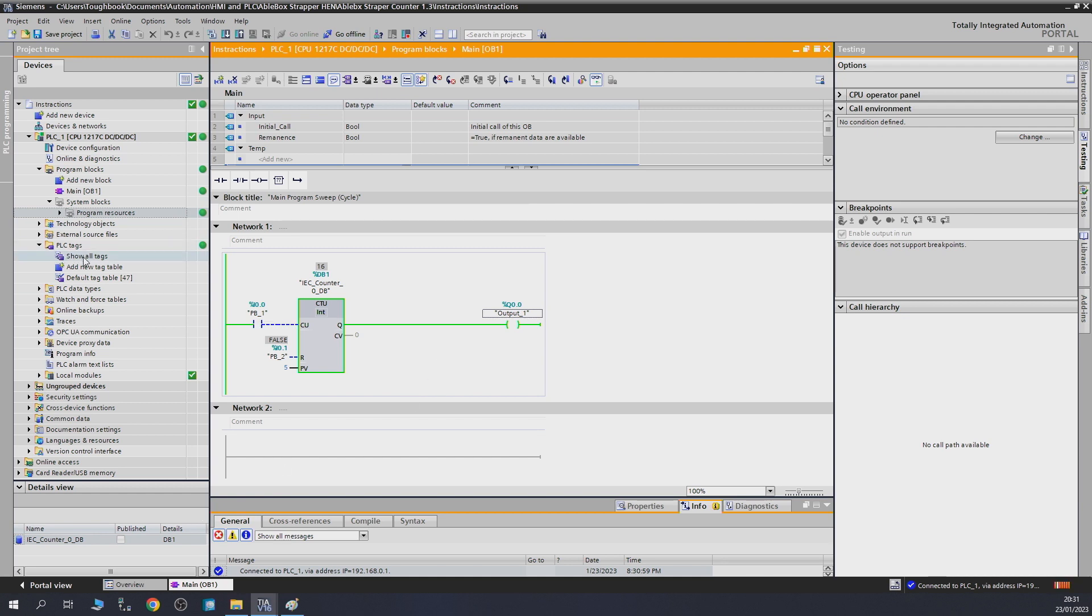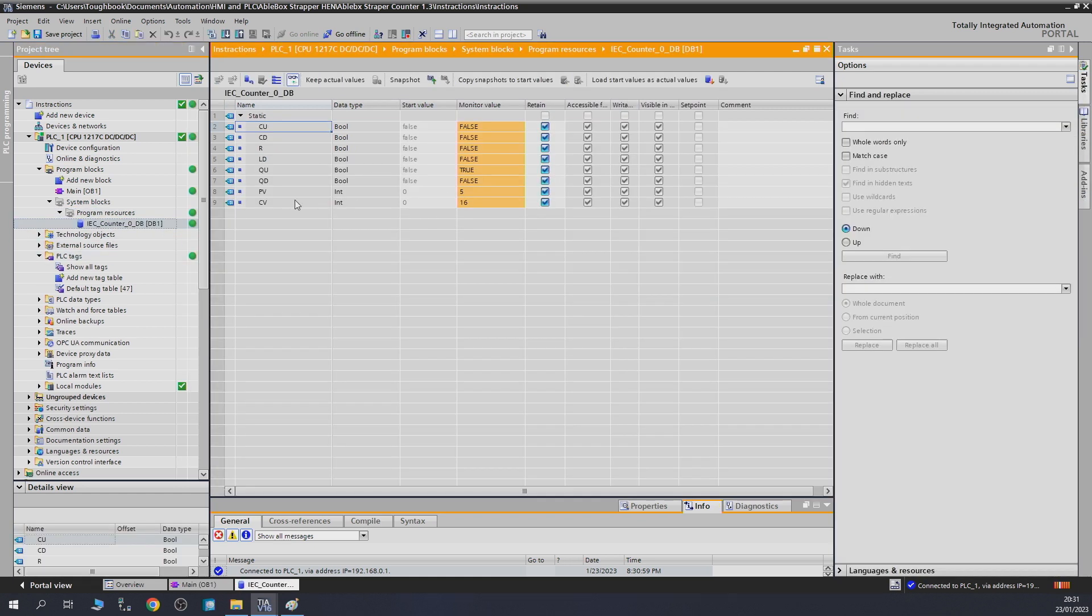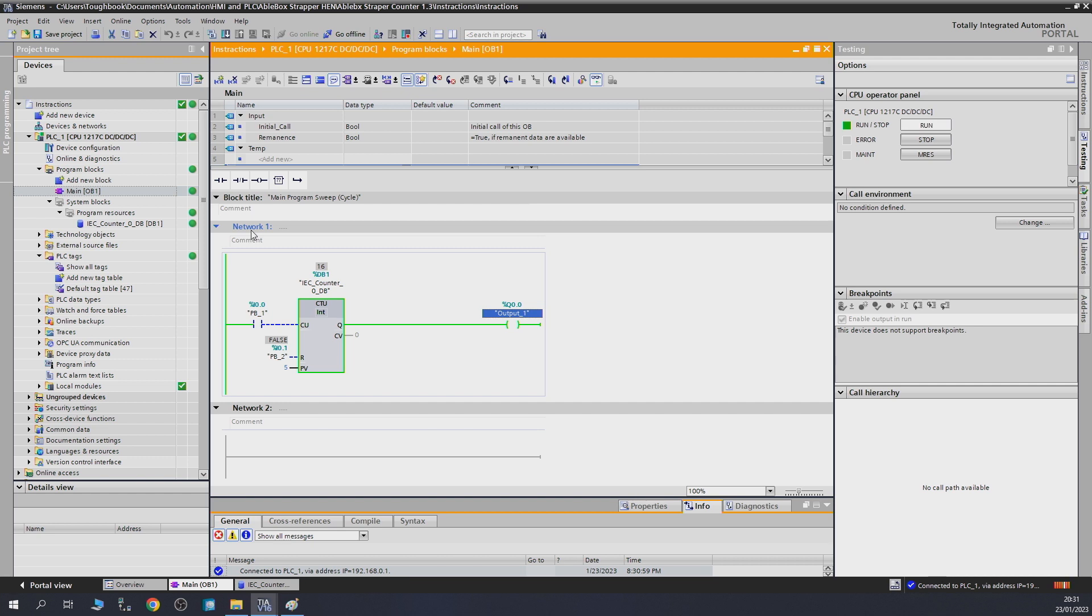If you look at the data block for it, as you can see the PV is five, but the CV we have done sixteen. The whole thing turns on at five, and after that it's useless for it to do anything because it's already done its job. For it to restart, all we need to do is reset it and it will reset back to zero. Then we can start again: one, two, three, four, five, and the counter goes on. That's how the counter up works.